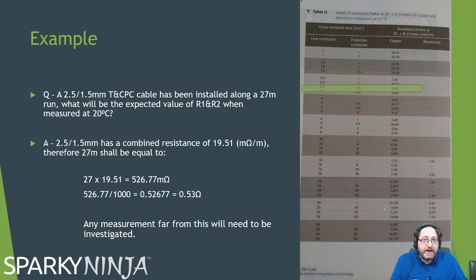This is the table from the on-site guide, and it tells you that the 2.5 mil 1.5 mil combined resistance is 19.51 milliohms per meter. I multiply that by the length of 27 meters to give me 526.77 milliohms. I don't want milliohms, I want ohms. So I divide by 1,000 to get 0.53 ohms. If I've measured 0.51, 0.54, 0.56, I'm happy. If I've measured 0.84, I'm like, don't like that. Okay? So make sure you can interpret information.